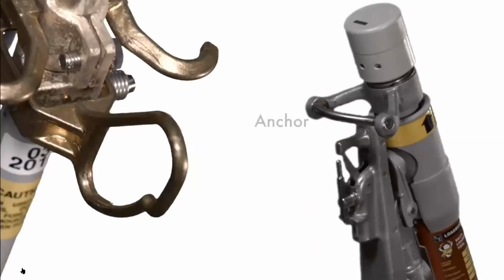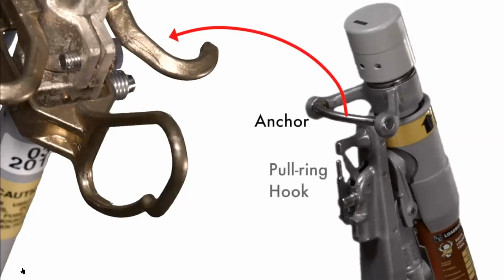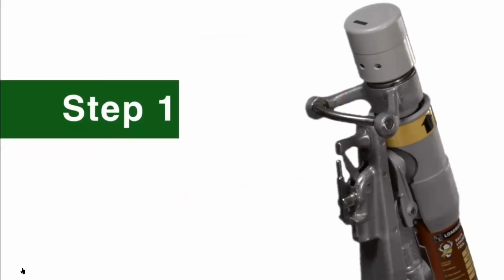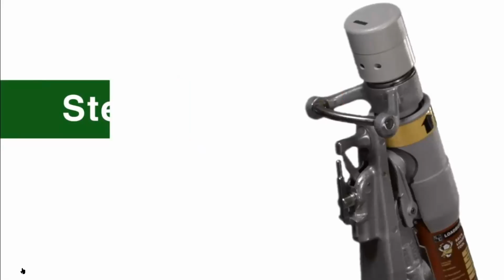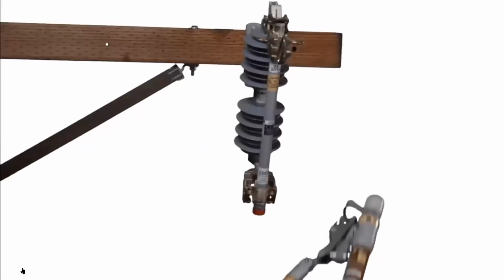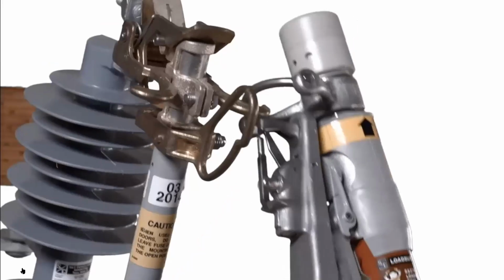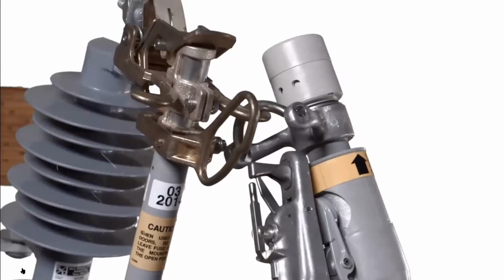The load buster tool has an anchor, which attaches to the attachment hook of the operating device, and a pull ring hook, which attaches to the device's pull ring. Step 1. Reach across in front of the SMD20 fuse mounting with the load buster tool and hook the anchor on the far side of the SMD20 mounting.